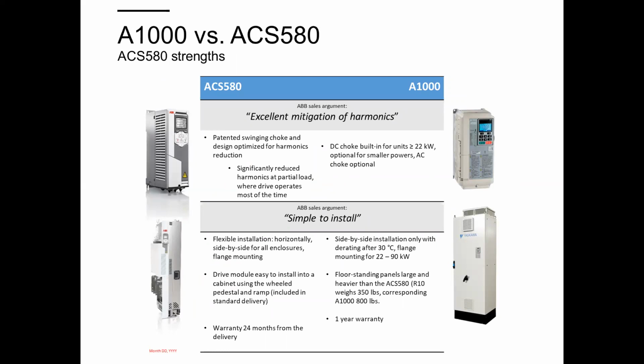In this slide, I want to compare the harmonics mitigation - in the 580 it's excellent because of the swinging choke, giving flexible installation. Yaskawa has a DC choke built in over 22 kilowatts. In terms of size, Yaskawa is really heavy and large.